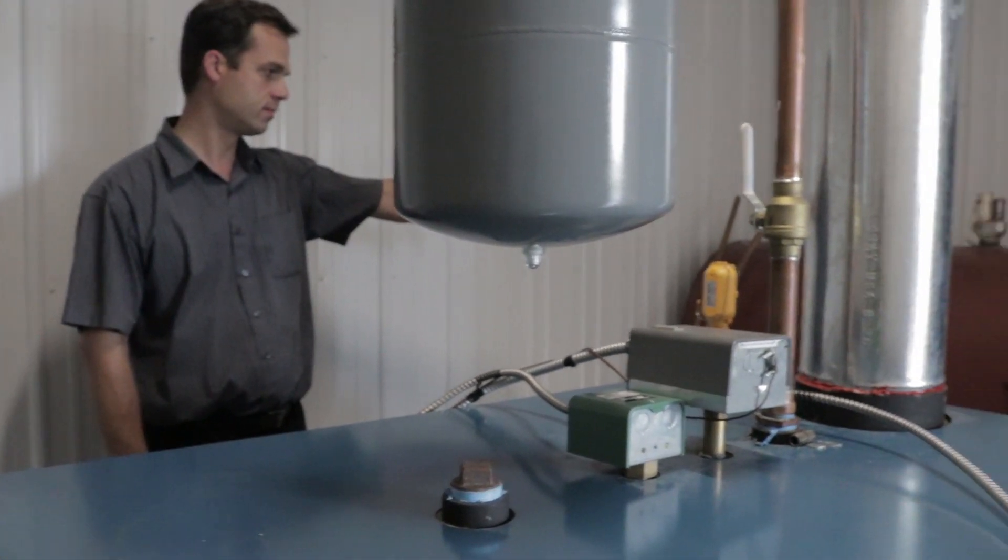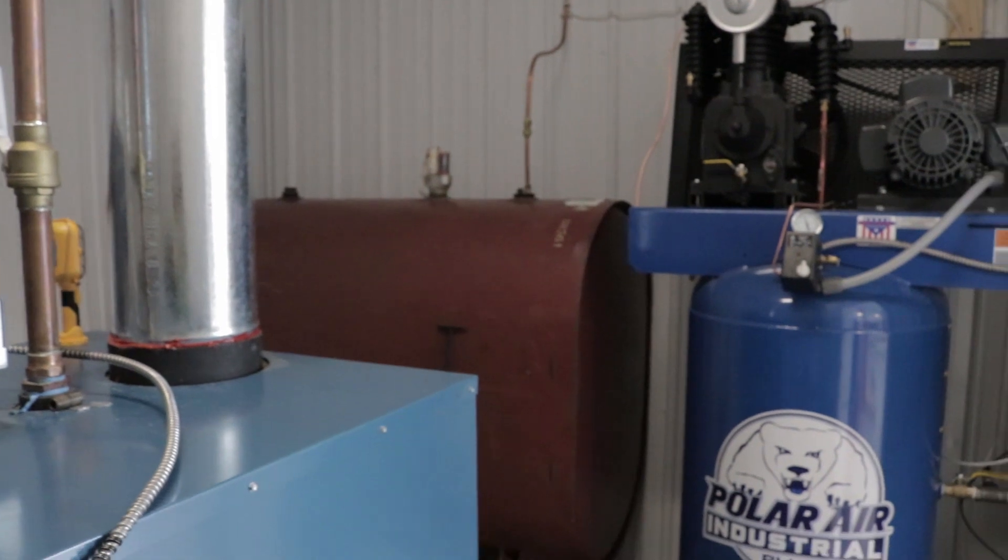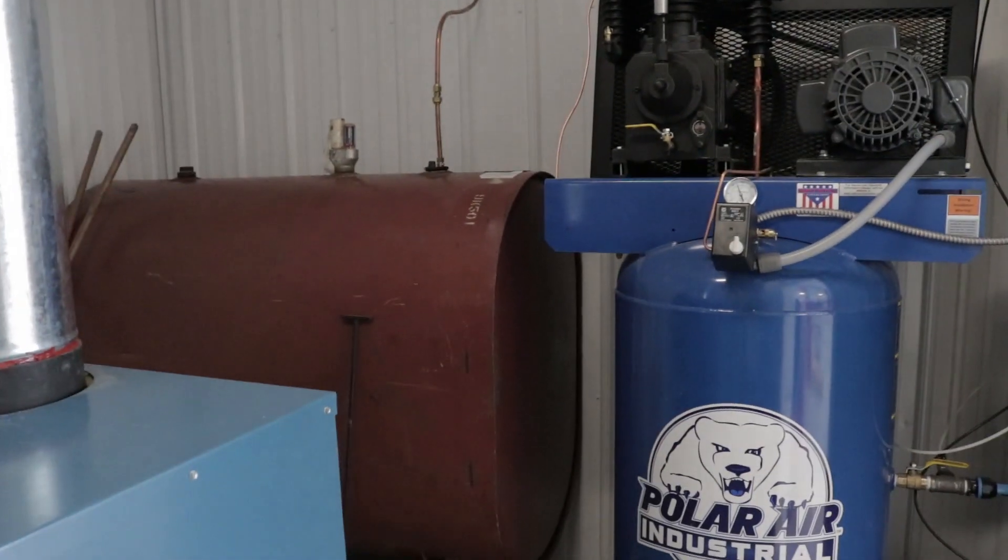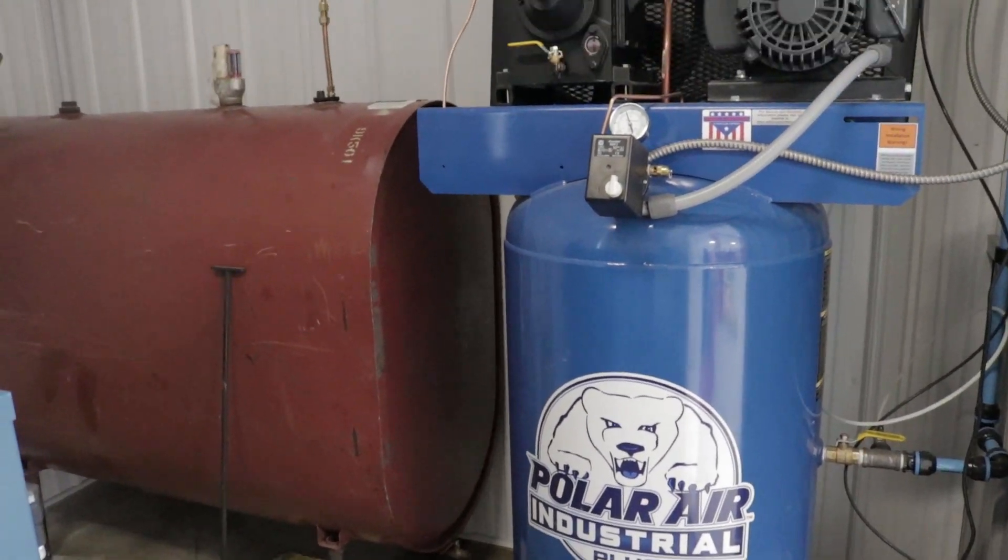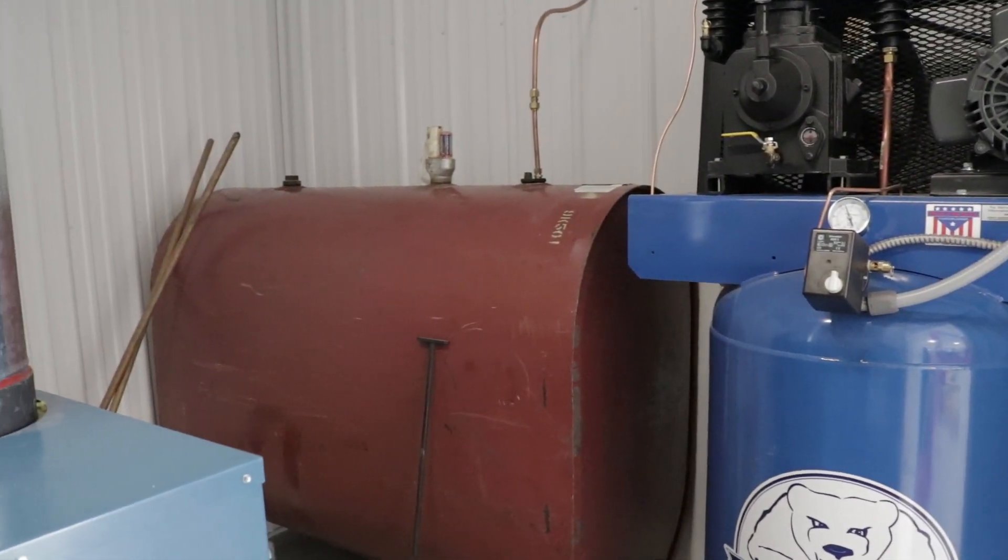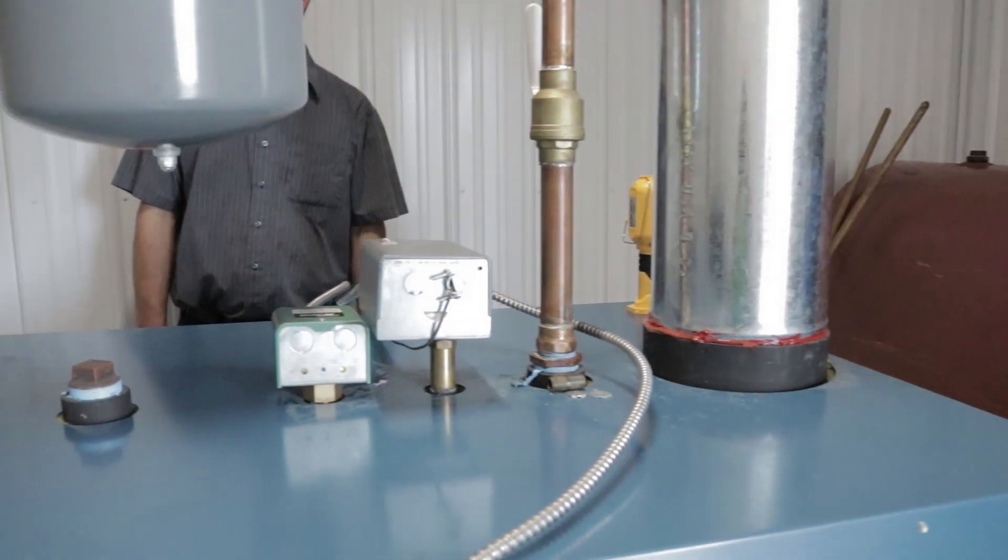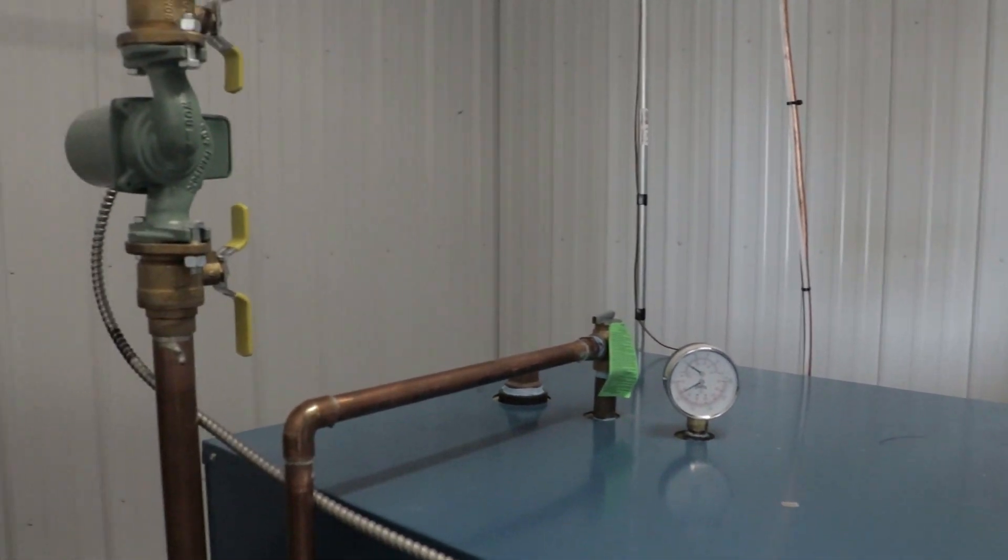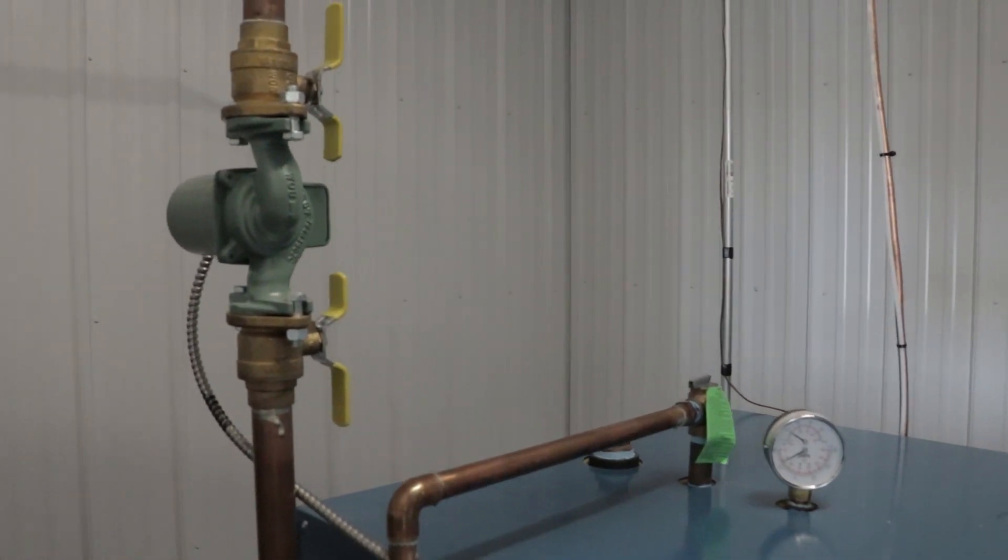is a storage tank, pump tank, and also compressed air. So you will need to supply an air compressor and a storage tank. And also 20 amp service from a dedicated breaker in your service panel. And of course make up water.